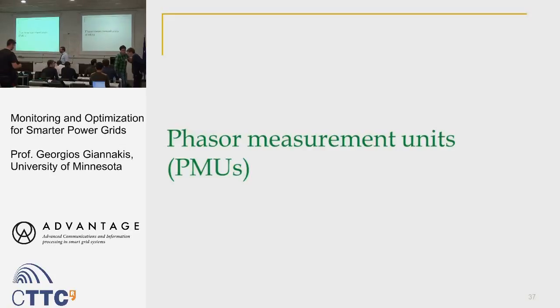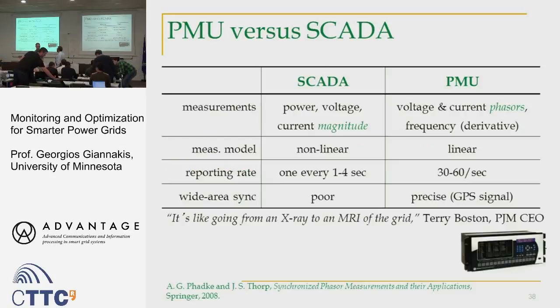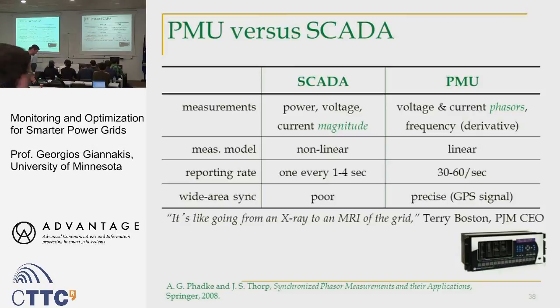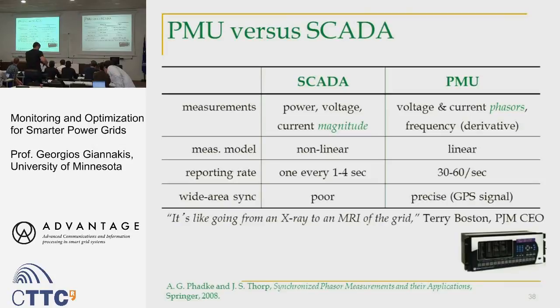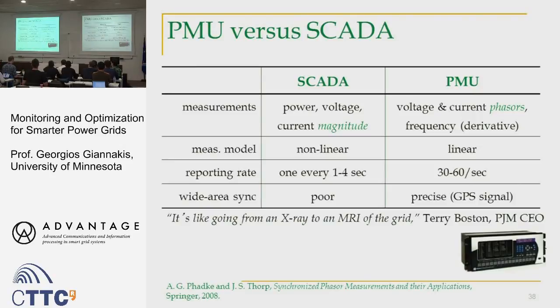The next segment deals with PMUs and these have to be contrasted with conventional meters called SCADA. SCADA provides power, voltage, and current magnitudes — only magnitudes. It reports a measurement every one to four seconds, and the synchronization is poor across areas.